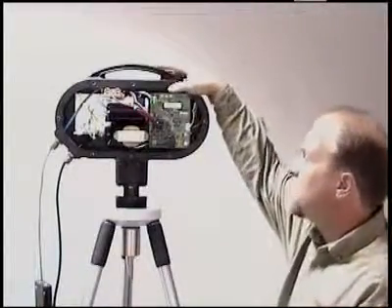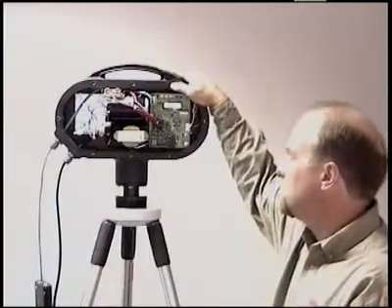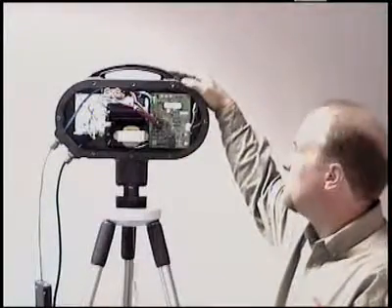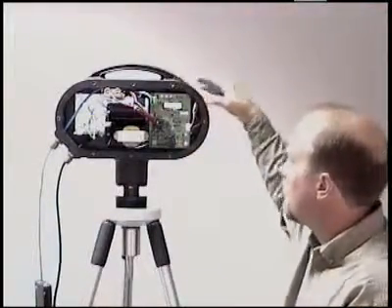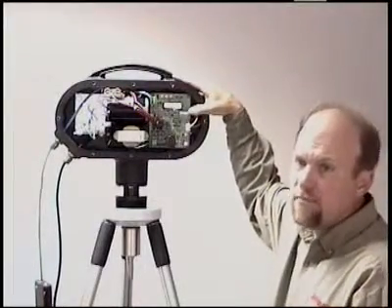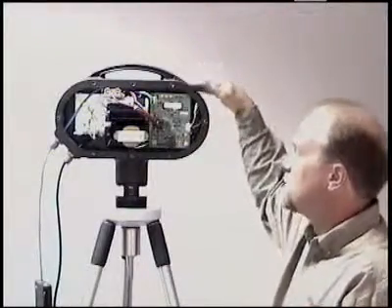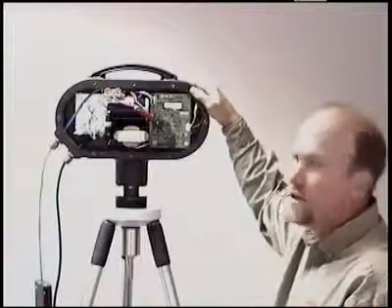We can cycle the unit with cycle buttons from the very top, so if we want to troubleshoot, we can actually cycle it while we're on top of the vessel. There are dip switch panels to set every remote with an individual address so that when we communicate, we know exactly which one we are communicating with.